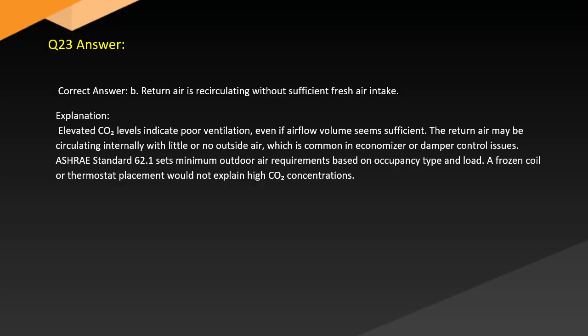Answer. Correct answer: B. Return air is recirculating without sufficient fresh air intake. Explanation. Elevated CO2 levels indicate poor ventilation even if airflow volume seems sufficient. The return air may be circulating internally with little or no outside air, which is common in economizer or damper control issues. ASHRAE Standard 62.1 sets minimum outdoor air requirements based on occupancy type and load. Frozen coil or thermostat placement would not explain high CO2 concentrations.